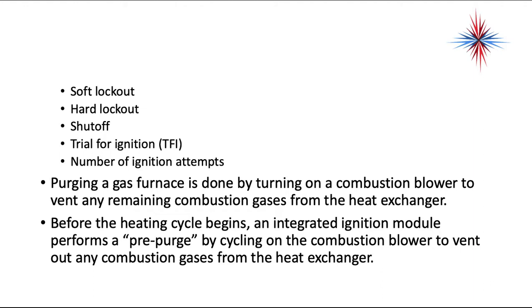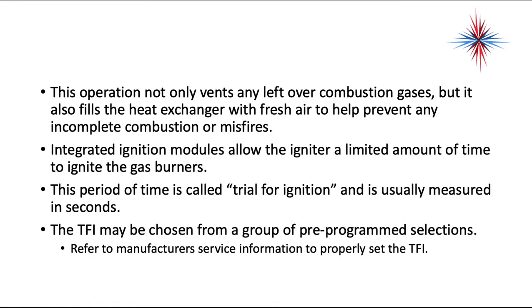Purging a gas furnace is done by turning on the combustion blower to vent any remaining combustion gases from the heat exchanger. Before the heating cycle begins, an integrated module performs a pre-purge by cycling on the combustion blower to vent out any combustion gases from this heat exchanger. This operation not only vents leftover combustion gases, but it also fills the heat exchanger with fresh air to help prevent any incomplete combustion or misfires.